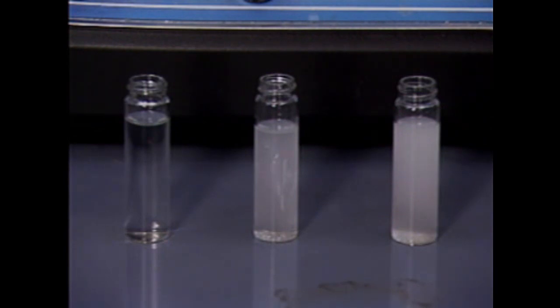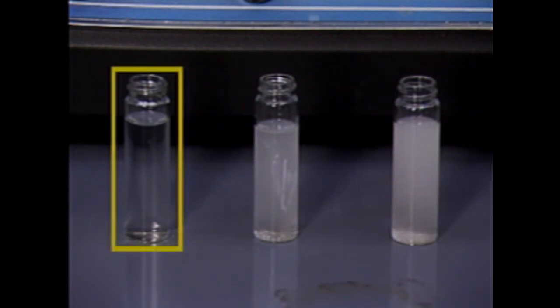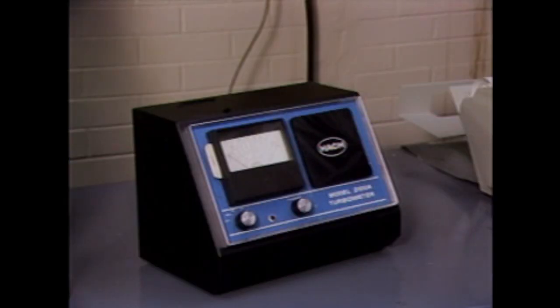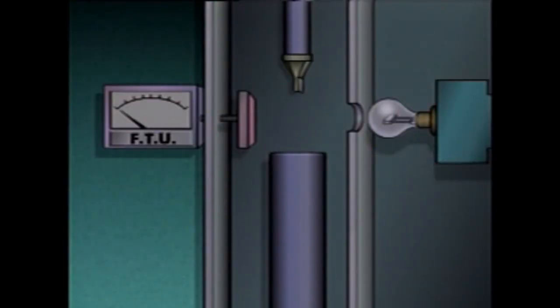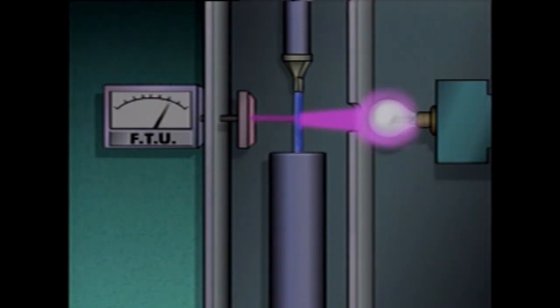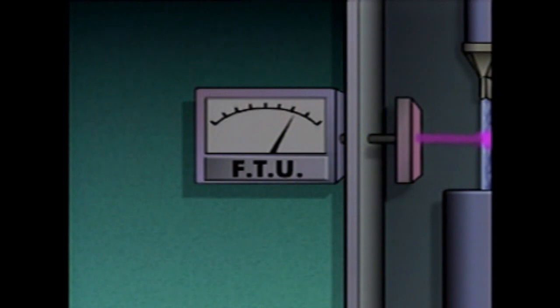The cloudiness or turbidity of a liquid varies according to the concentration of suspended particles in the liquid. A clarity analyzer that measures the turbidity of a mixture is called a turbidity meter. During operation, the liquid being tested passes through a special restriction that forms the liquid into a flat stream. A beam of light is then directed through the flat stream of liquid. Suspended particles in the liquid absorb and scatter some of the light, but the rest reaches a photometer. The amount of light that reaches the photometer depends on the amount of suspended particles — the more particles, the less light. The light measurement from the photometer is an indication of turbidity, expressed as formazin turbidity units (FTUs) or as a percent concentration of suspended solids.